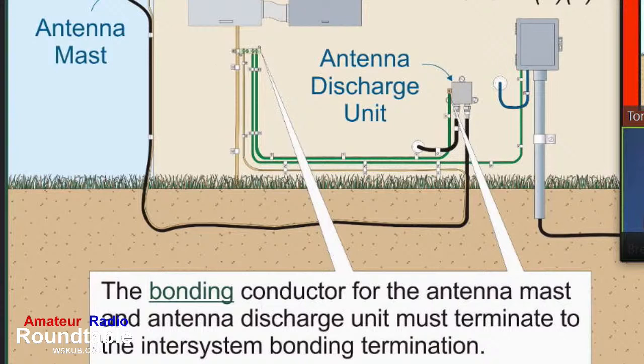Now, the rule, if you have an antenna mast on your house for a ham radio, you've got to ground it the same way. Basically, the rule is that it needs to be at least as thick as any conductor in the antenna. If you have a very thick, heavy antenna wire, you need to make it thicker. But it should also be a minimum of 10-gauge wire if it's copper, or 8-gauge wire if it's aluminum.